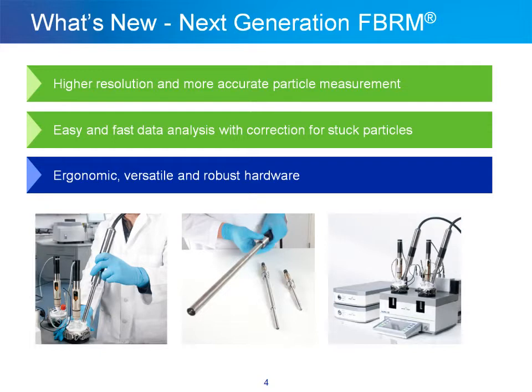In the Next Generation FBRM, we've completely re-engineered the FBRM hardware from the ground up. We've developed a new ergonomic probe design which easily integrates into a laboratory reactor. We've developed a versatile, interchangeable probe platform where a user can switch between probes on a given backend in a given electronics box. We've also developed robust hardware which can be easily installed in a laboratory hood or reactor, and it increases the time between service intervals.